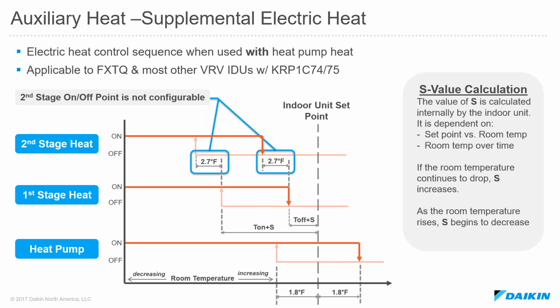So one great thing about the FXTQ and the logic built into it, and also the control options for our other indoor units, is there is really no concept of calculating a balance point. It's a supplemental heat source.